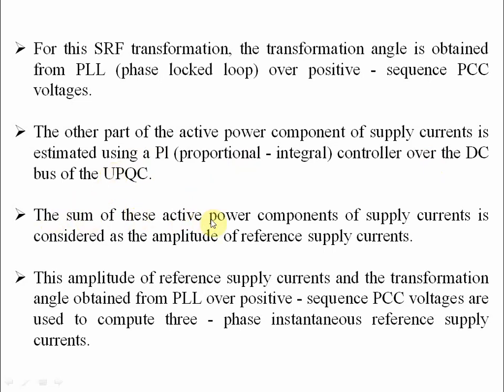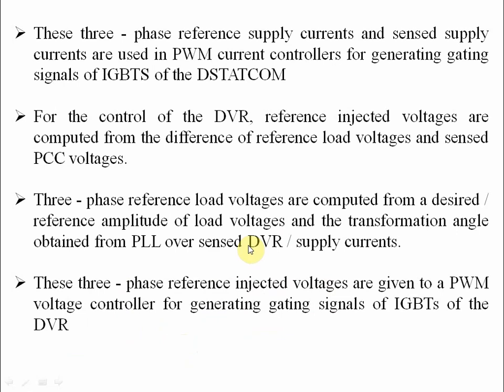The other part of the active power component of supply current is estimated using a PI controller over the DC bus of the UPQC. The amplitude of the reference supply current and the transformation angle obtained from the PLL over positive-sequence PCC voltages are used to derive the three-phase instantaneous reference supply current. The sensed supply currents and the derived three-phase reference supply current are then used by the PWM current controllers for generating the gating signals for the IGBT switches of the DSTATCOM.